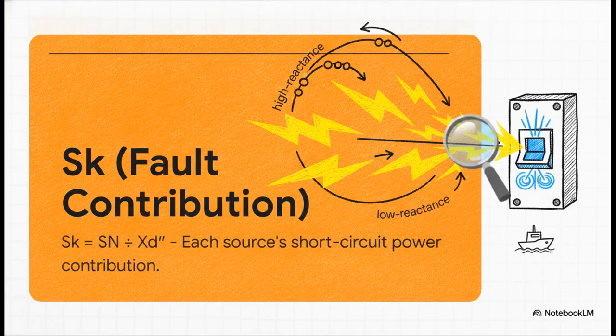Now, what's really interesting about this slide is how we actually calculate that individual contribution, SK, for each source. You find it by taking the apparent power of the machine, SN, which is just the total electrical power it's built to handle, and you divide it by something called subtransient reactance, represented by Xd double prime. Think of subtransient reactance as the machine's immediate electrical resistance to sudden changes. And here is the secret to understanding this formula. Lower reactance machines actually dump way more fault current onto the bus. So if a generator has a really low subtransient reactance, it is going to unleash a massive, instantaneous spike of power the exact millisecond a short circuit occurs. That violently high number, that is exactly what your breaker needs to be tough enough to survive.